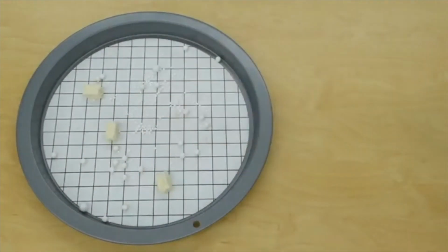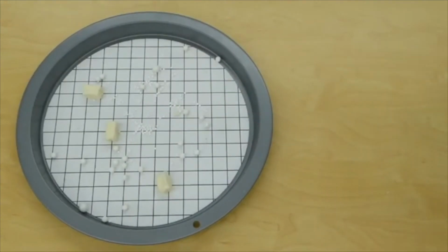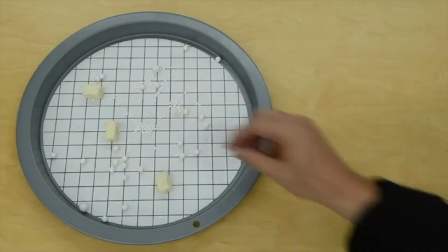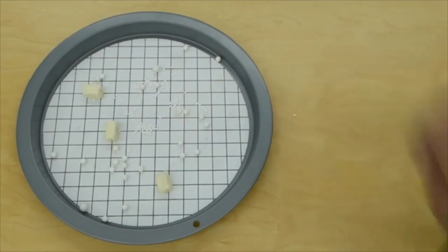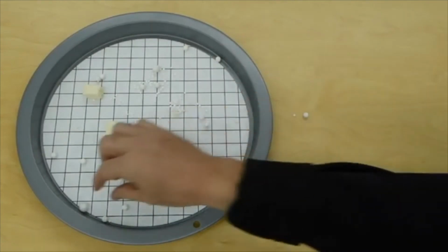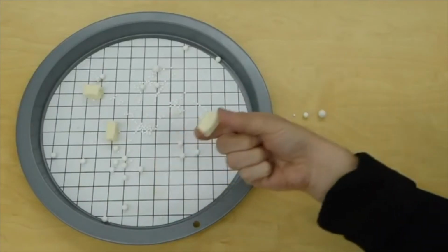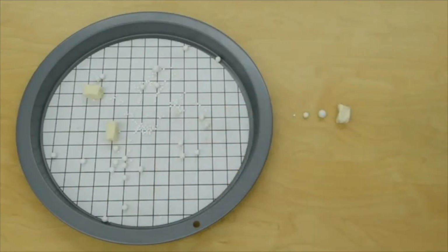Now, ultimately, I could just say, look, this is how many particles I have. But you know what? It's going to be more useful to me if I know the particle distribution. How many small particles, medium particles, and large particles? That's going to be better information, and I could be more equipped to make a decision. So I've got different size particles in here. I've got really small ones, some larger ones, some larger ones again, and some terrifying big chunks that look quite damaging to our system.